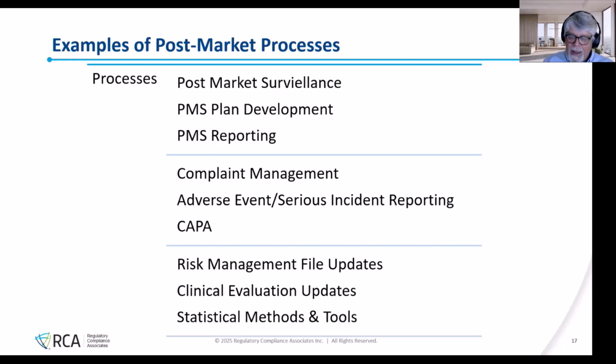The input to that is the complaint management system, the complaint process. I think it's a misnomer to call it a complaint sometimes. The complaint can be either good or bad, and I take it to be more of clinical experience using the device, whether it's good or bad. It's clinical experience that we're going to use to ensure that the device is safe for intended use and has effective performance. Part of the complaint management system, if you do get some sort of complaint and somebody's been hurt or there's been an adverse event, there are very strict rules by country on what you need to do. And there are time limits that you have to meet. And there's reporting. Clearly, when you get to adverse event and serious reporting, your company is in a legal liability situation.